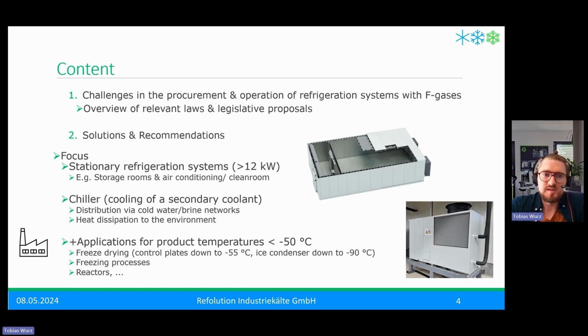For example, we will talk about stationary refrigeration systems above 12 kilowatt. These are some kind of categories you find in the F-gas regulation. On the right we have storage rooms or air conditioning, like direct evaporation systems. You have clean rooms. Chillers are a very important sector because it's a separate category in the F-gas regulation, meaning you cool a secondary coolant. Here on the right you have a normal chiller, but for example if you have a freeze and thaw unit with oil inside at minus 80 degrees, it's technically a chiller too because it cools down a secondary coolant.